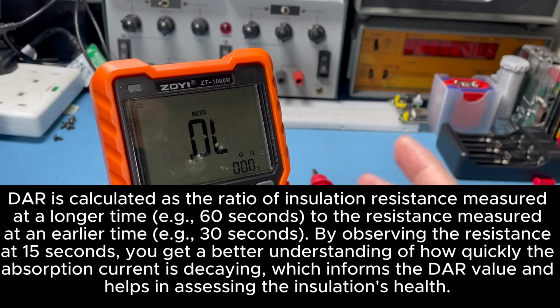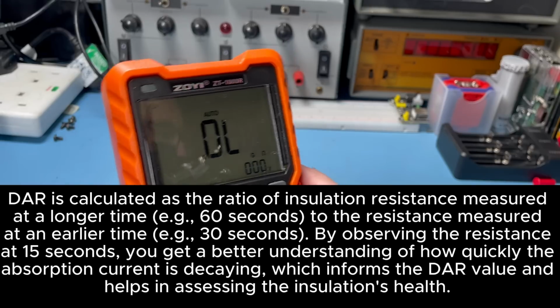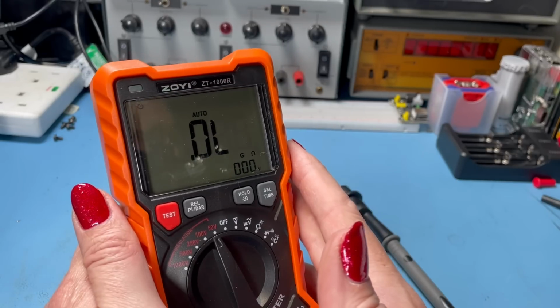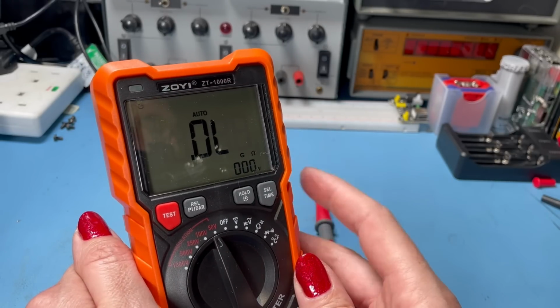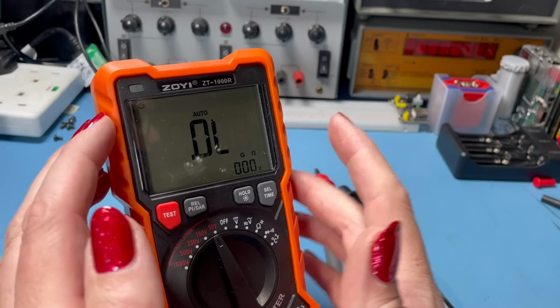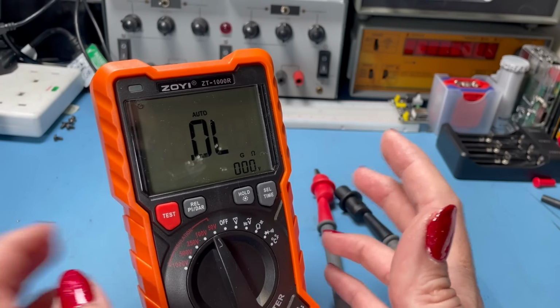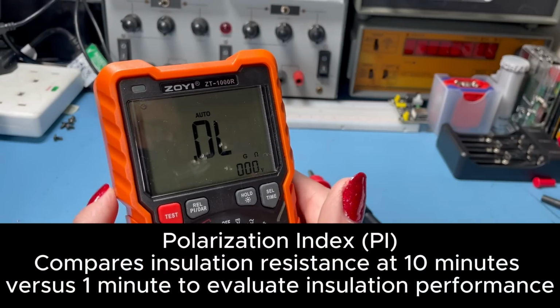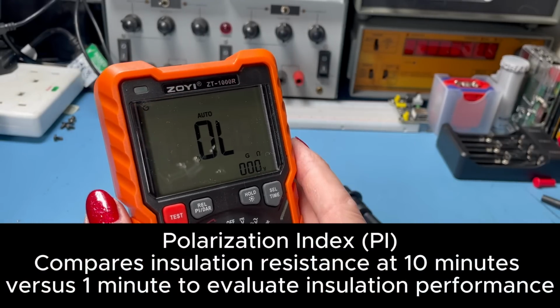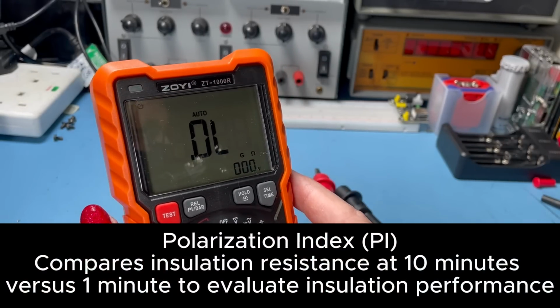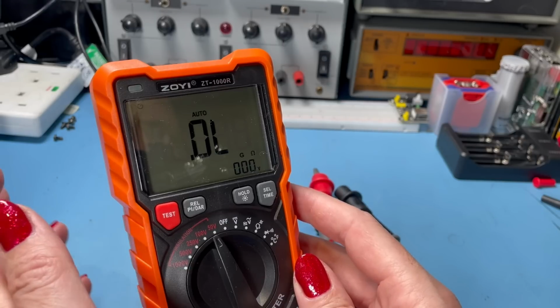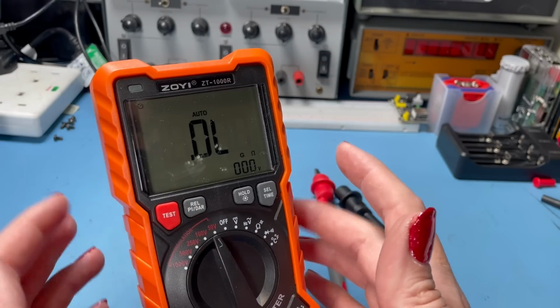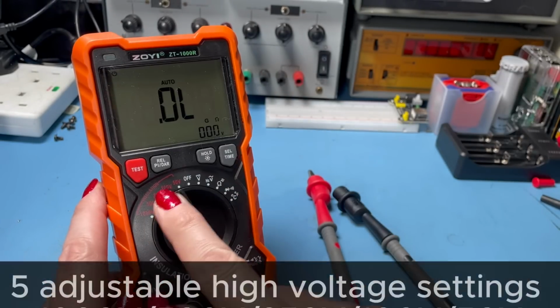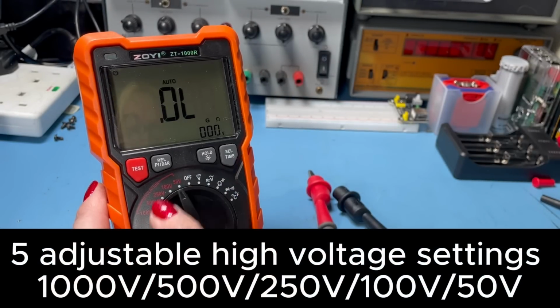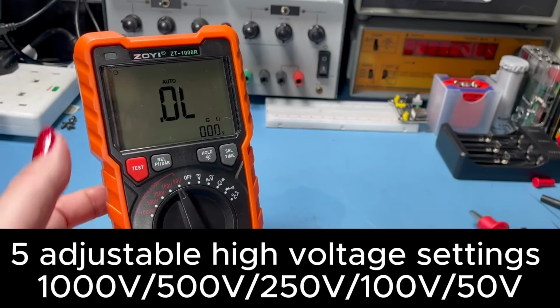Now 30 seconds is a common standard in DAR calculations, but some people do prefer to use 15 seconds. There is one school of thought that says it allows for a more sensitive observation of the initial absorption current behavior. With the PI, it's a longer test. It takes 10 minutes and it compares the insulation resistance at 1 minute to 10 minutes to evaluate the performance of the insulation. And of course you've got your 5 different voltages there that you can test at, depending on what you're going to do.